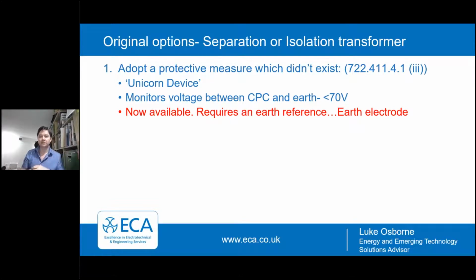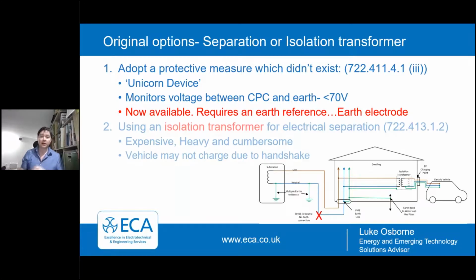The changes added in some additional things. So one of the existing measures was to adopt a protective measure which didn't at that time exist. So this was in 722.411.4.1 indent 3. It's a long regulation. This was colloquially known as the unicorn device, and this monitors the voltage between the CPC and earth to ensure that it remains below 70 volts. These devices are now available, but they do require an earth reference electrode. So this is a smaller electrode. This isn't to shunt the entire fault current down, so it's just a monitoring electrode. So that was one option, which still exists.